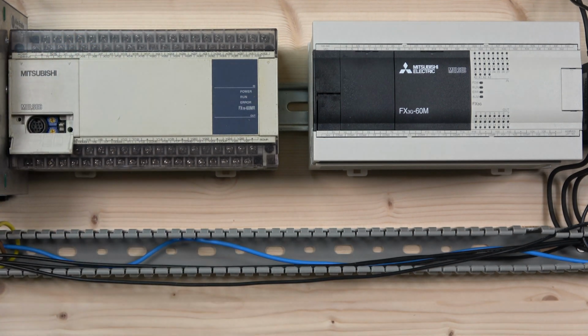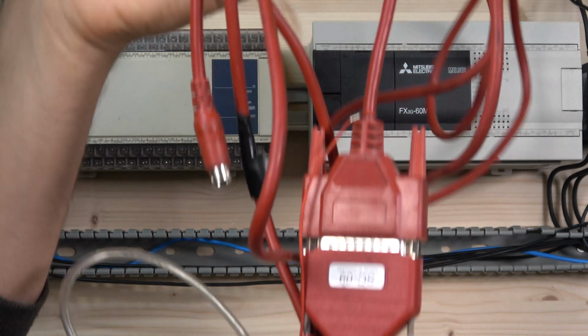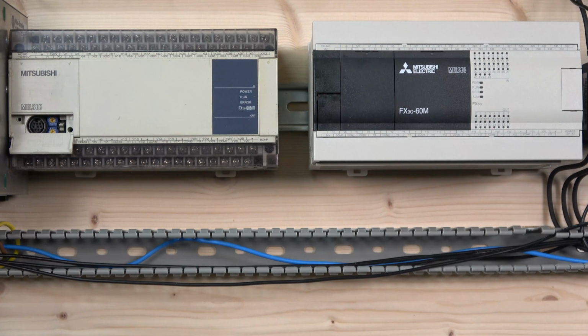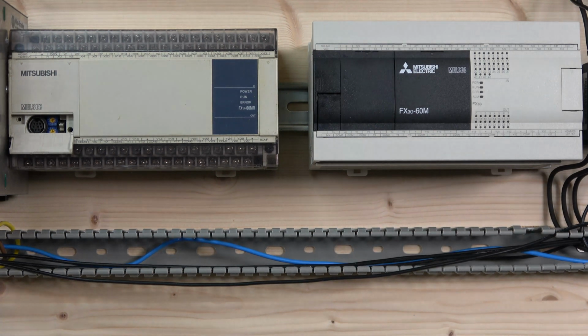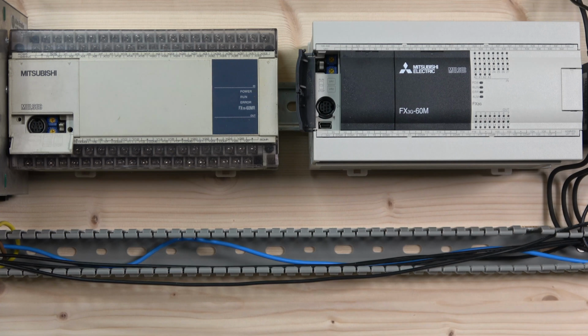Another difference is that, to download the program out of the FX1N, you will need the SC09 cable, which looks like that and has an RS232 port on the end. I will leave a link in the description to the video where I showed the little RS232 to USB converter, so we can download the program to our PC in case you don't have a laptop with an RS232 port. But this one has built-in USB, so you can connect directly, no need for any fancy cables. Just the USB will be fine.